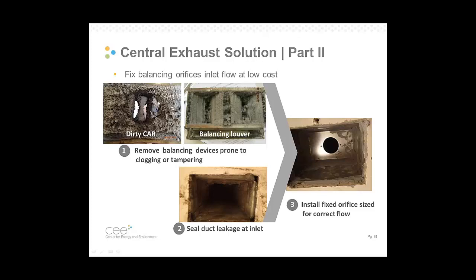One issue with these is that after a couple of years of operation, or as little as a couple of years, the pressure monitoring portion of this device gets crudded up. You can see that this one's pretty dirty after a few years of operation. It got pretty dirty, and it no longer self-adjusts. So that's a problem. Once they can't self-adjust anymore, they're just an orifice, so they don't have the ability to balance anymore.